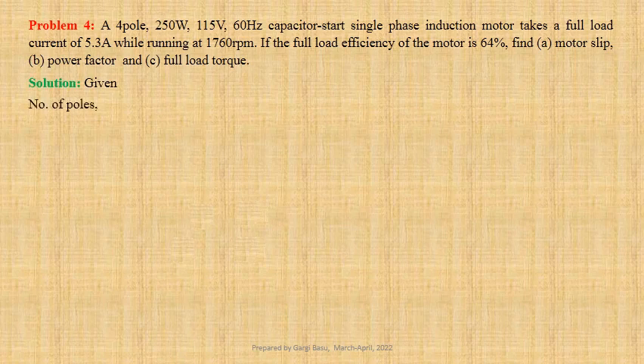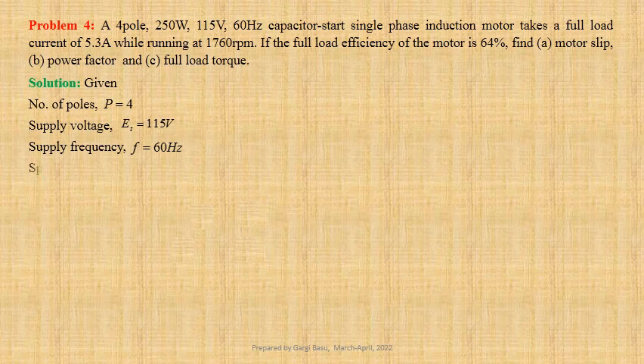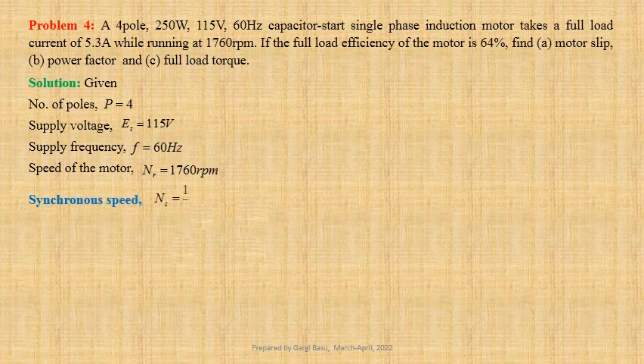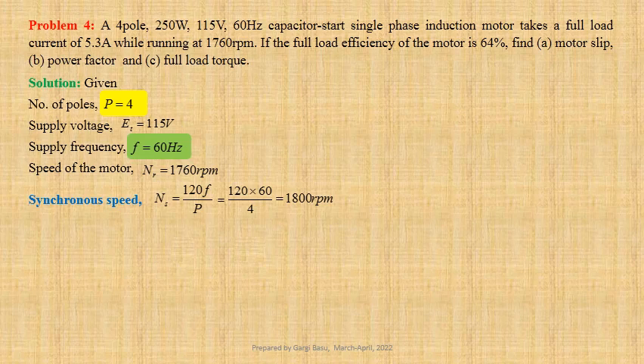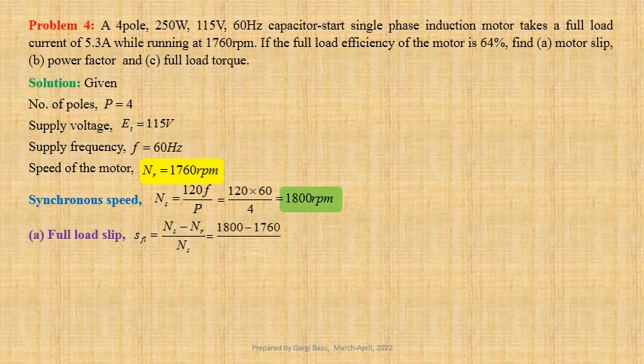Number of poles of the machine P equals to 4. Supply voltage Et equals to 115 volts. Supply frequency F equals to 60 hertz. Speed of the motor Nr equals to 1760 revolutions per minute. Let us now determine synchronous speed. Ns equals to 120F by P. Using values we get 120 into 60 divided by 4, that gives us 1800 revolutions per minute. Full load slip SfL equals to Ns minus Nr divided by Ns. Using values we get 1800 minus 1760 divided by 1800, that gives us 0.0222 per unit or 2.22 per cent.